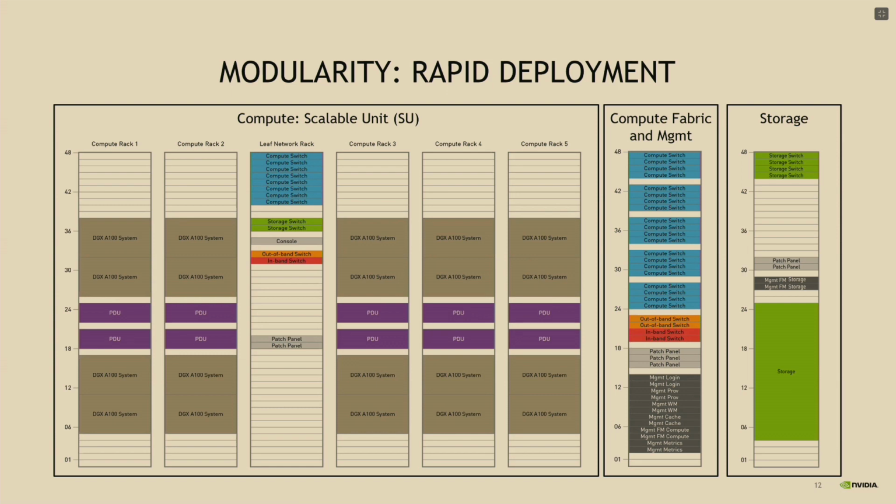So don't take this too literally, because there are different ways to deploy. We shot for 4 machines per rack because this fits in 28 kilowatts, which is the most common high density rack design that we see. We have some customers that need to go in telco racks, and so they will have 1 machine per rack, maybe 2. And then we have some very high density customers that may even go up to 8 machines in a single rack.